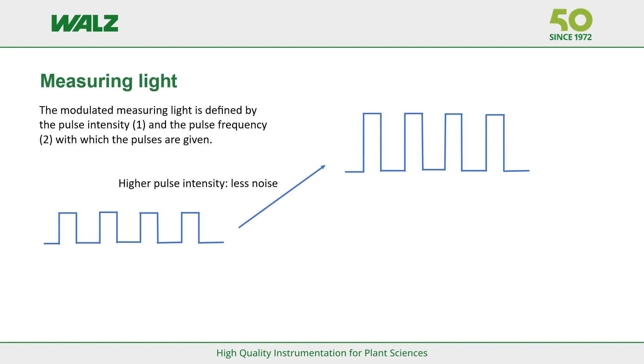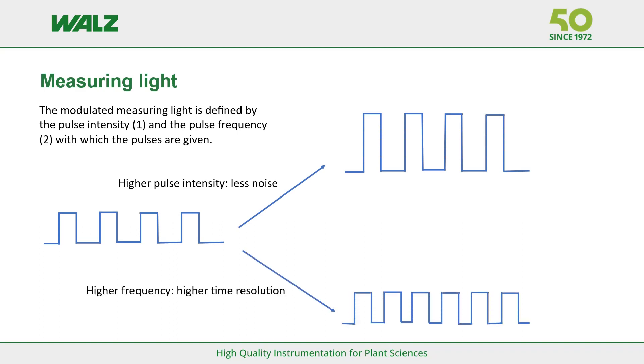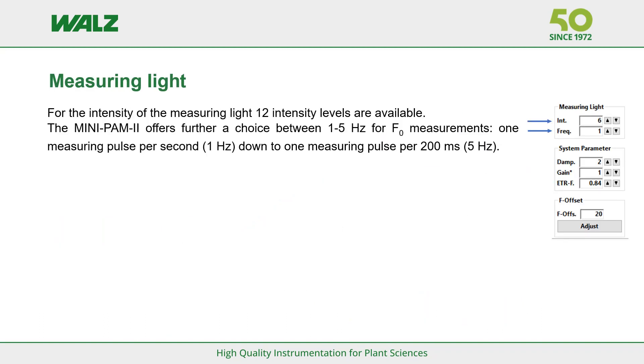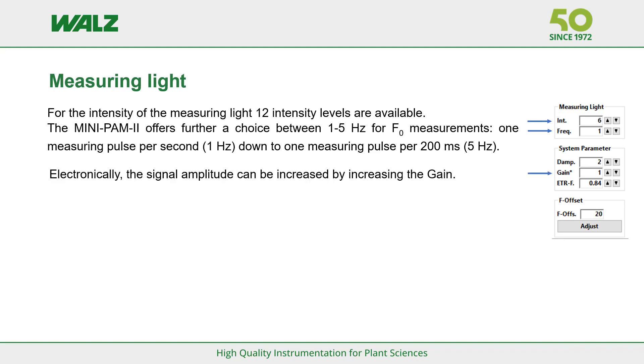If the pulse intensity is increased, signal noise will decrease. If the pulse frequency is increased, the time resolution of the measurement is increased. By adjusting pulse intensity and pulse frequency, it is possible to control the integrated light intensity. For the MINI-PAM-II, twelve measuring light intensities are available. In the WinControl software, it is possible to choose between 1 to 5 Hz for F0 determinations — that is 1 pulse per second down to 1 pulse per 200 milliseconds. The signal intensity can also be increased by the gain, which increases both signal amplitude and noise but has no effect on integrated light intensity.